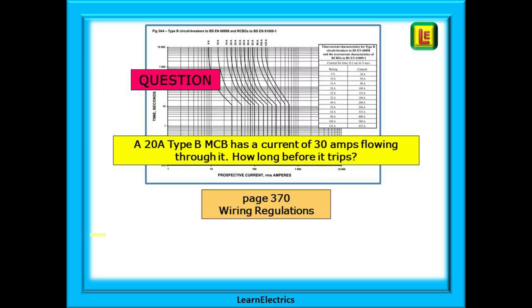So how do we use this graph? We can show you best with an example. A 20 amp type B MCB has a current of 30 amps flowing through it. How long will it be before it trips? And the answer might surprise you.